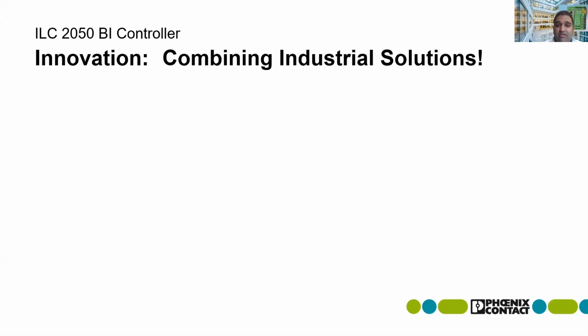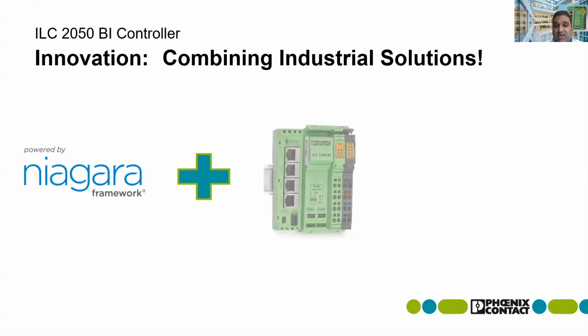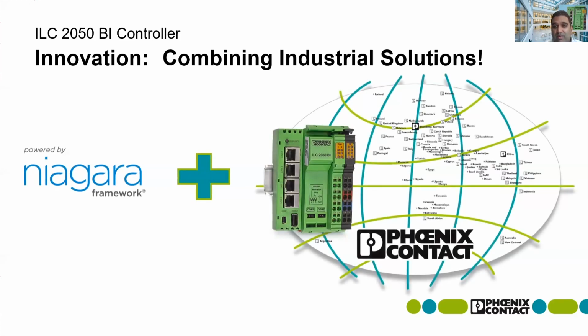With our combining solutions, what we have is a controller that is a building management controller. It's a controller that sits on the Niagara framework. For those not aware, Niagara is a software platform that looks at integrating many subsystems or protocols of a building system onto one single software platform. It's basically owned and run by Tridium, or Honeywell if you want to call them, but it allows multiple subsystems or protocols to talk onto one single, quite intuitive software platform.